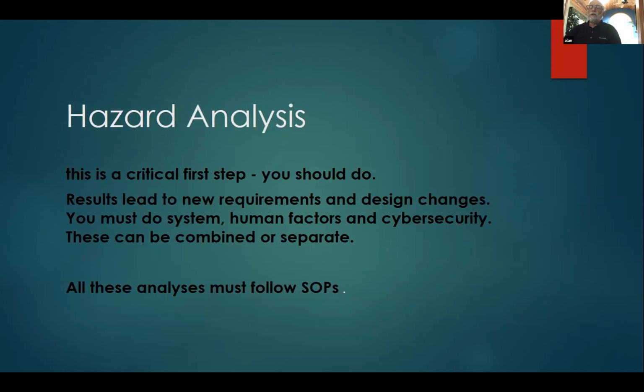The last part is the hazard analysis. This is a critical step for your software. The results lead to new requirements and design changes. You must do a system, human factor, and cybersecurity analysis. These could be combined or separate. All these analyses must follow written SOPs. Hazard analysis is part of your design control. The FDA is expecting that you've done this in order to remove as many hazards as possible, and if they aren't removed, that there are warnings in your instructions for use on what the user or the patient should be doing as part of any potential open hazards.